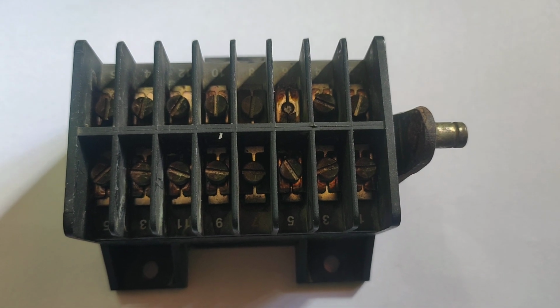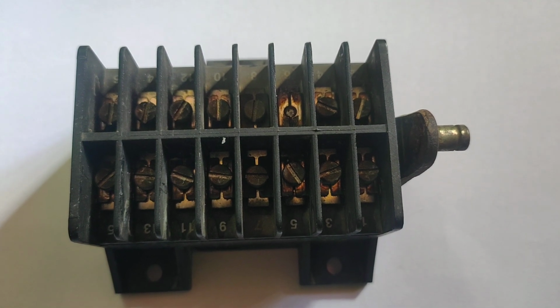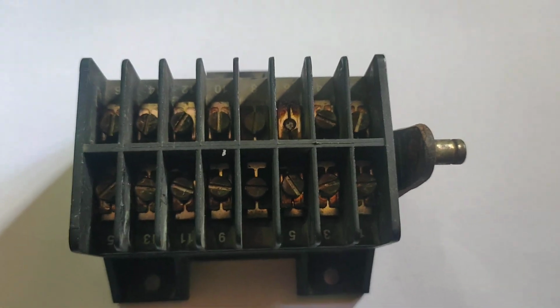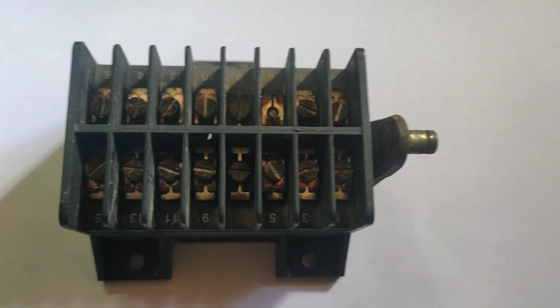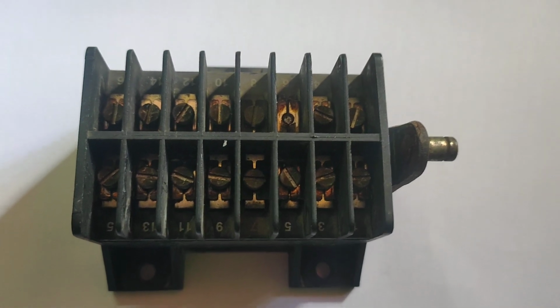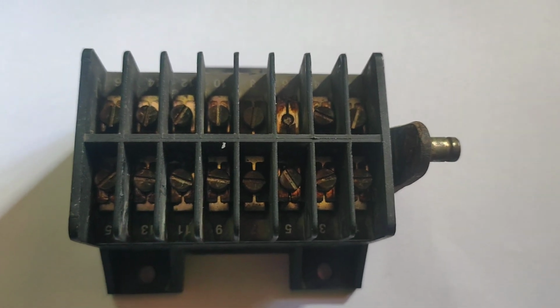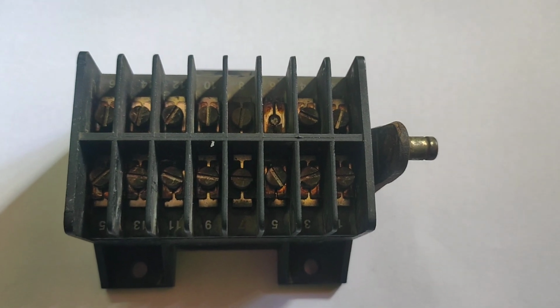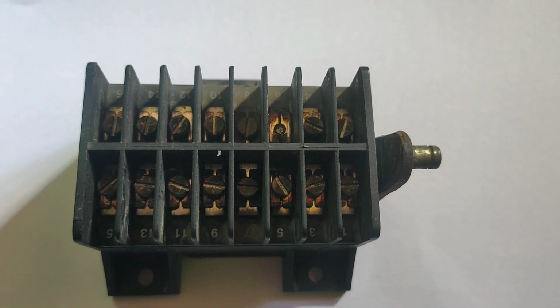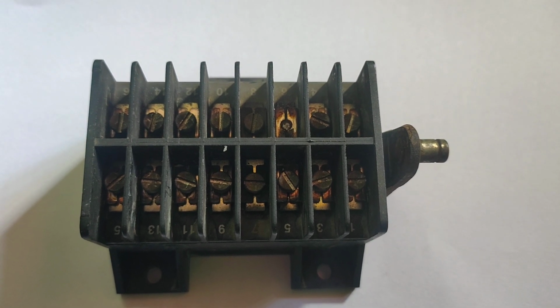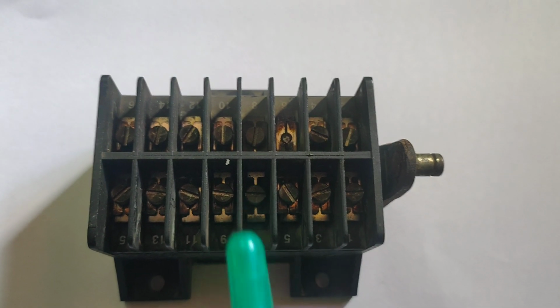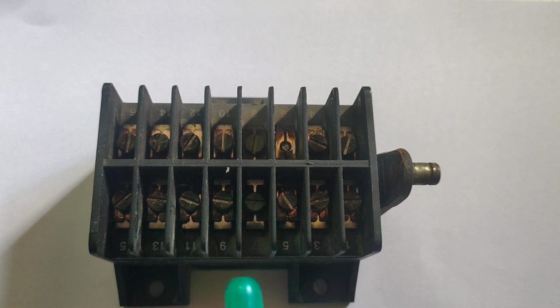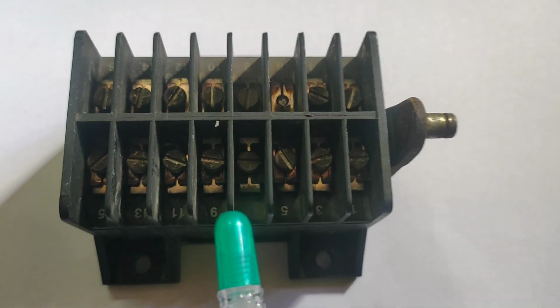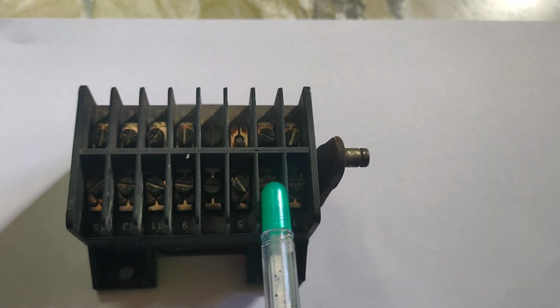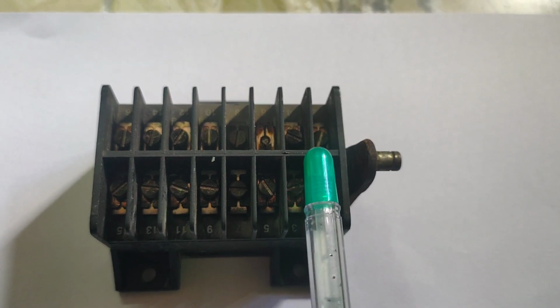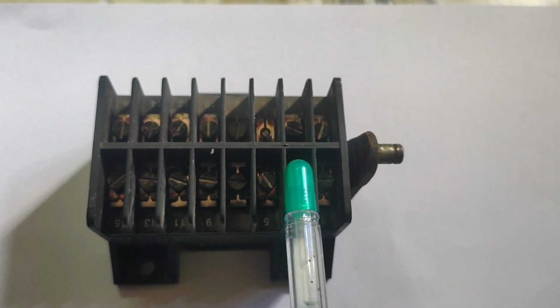Inside this circuit breaker, the DM box, drive mechanism box, these auxiliary contacts are present. If you see my previous video about the control circuit, there you will see the S1 contact present. This S1 contact controls the closing path of the circuit breaker, tripping path of the circuit breaker, pole discrepancy of the circuit breaker, SF6 low.